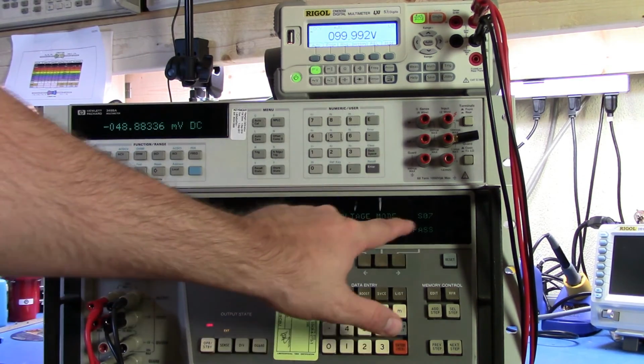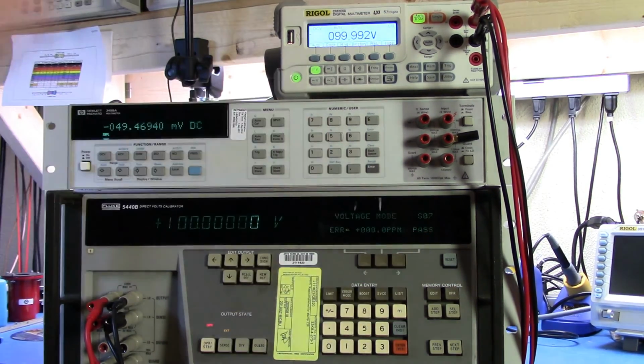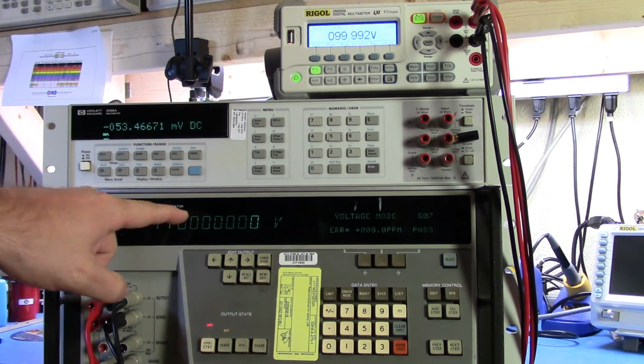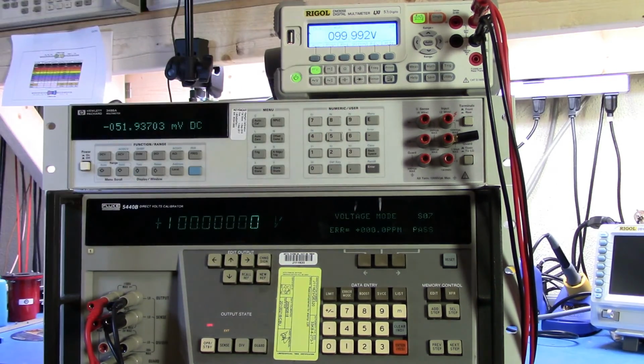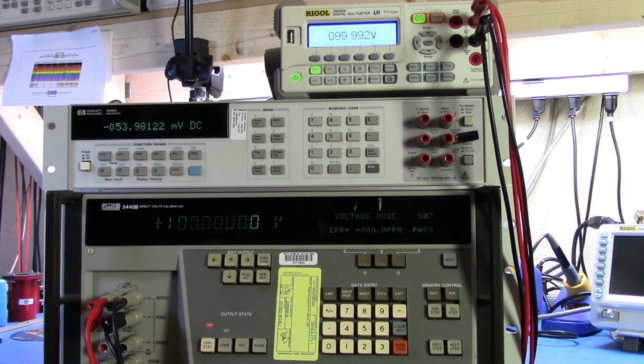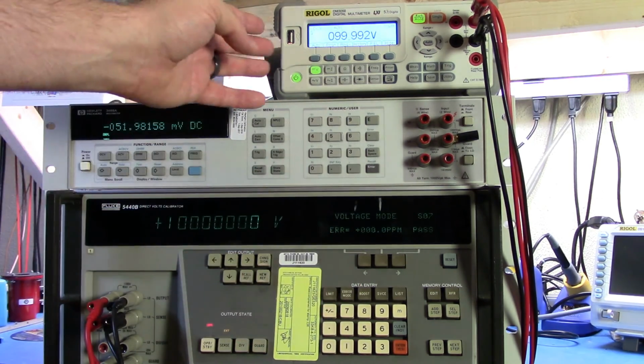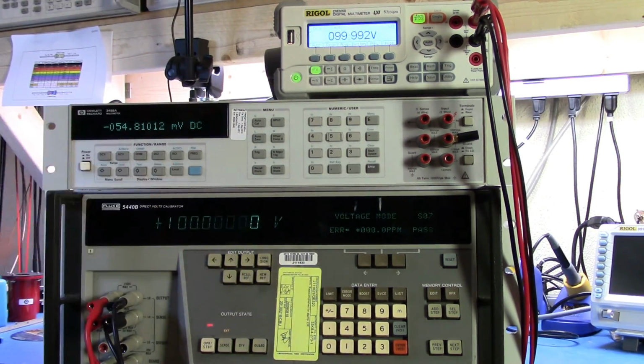At the end of this whole process, what I will have gotten is a set of values for whether or not my unit is actually in calibration. So this makes it really easy for you to go in and calibrate meters, especially for DC. Well, this is DC only. You can calibrate these meters because you can set all this up and then store that there.